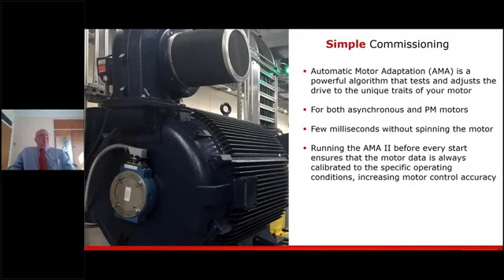Now, many VSDs offer a similar function today, but different to many competitors, the Danfoss drive performs this auto tuning without spinning the motor and without the need to decouple the motor from its load, be it a conveyor, a pump, or a fan. And this saves time during the commissioning. But most importantly, it typically ensures that the procedure is done during commissioning. And if the motor has to be decoupled, quite often this tuning is overlooked during the commissioning phase, mainly due to time pressures. And then this will result in the plant operating at less than optimum performance for its lifetime.